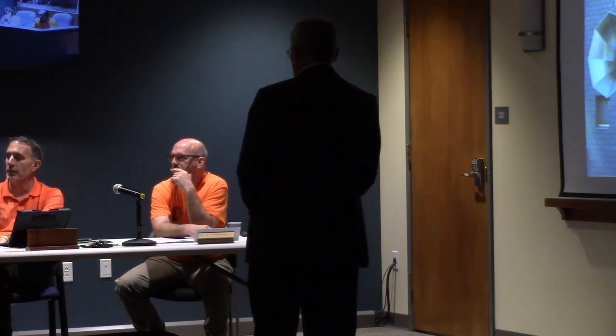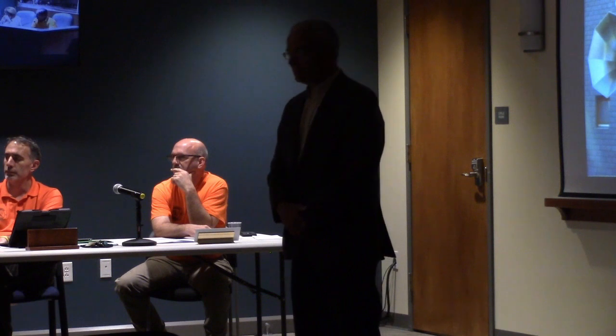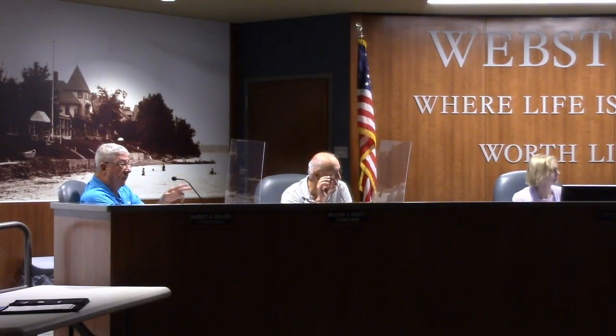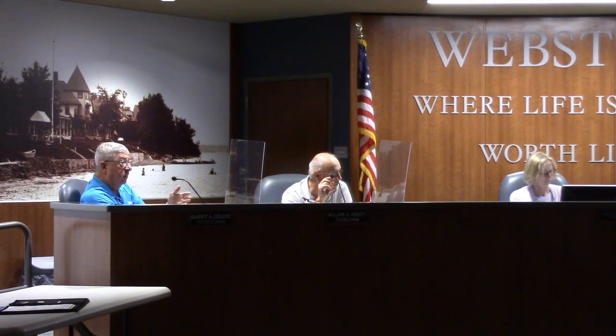Art, what's your budget for your disposal this year? $500,000. So in theory, from what we're talking about, 25% solid, 75% water, if that dryer works the way you're talking about, we're talking about a 75% reduction in landfill. John, I mean, right here you're saying only 25%. But what we talked about earlier is that the sludge we're hauling away right now is 25% solid, 75% water. We get rid of 75% of water, that's 75% of that $500,000 that should be saved. Again, these are very conservative numbers, and we wanted to stay very conservative. John, the facility that Rick and I toured back in the fall in Pennsylvania, they're on their second generation of dryers, and they give their Class A biosolids away for free.